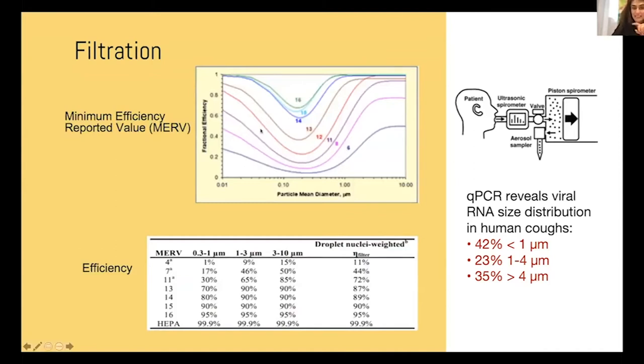So this graph shows, the one on top, efficiency on the y-axis. On the x-axis, it shows particulate size. The first thing to notice is that it's basically an inverse bell curve. And you see the lowest efficiency is somewhere between 0.1 to 0.3 micron. What does this mean? Above 0.3 micron, filters are very efficient. Below 0.1 micron, filters are very efficient. So when you hear that HEPA filters are certified at 0.3 micron, it doesn't mean they cannot remove particles below 0.3 micron. It means this is the point where they have the lowest efficiency.